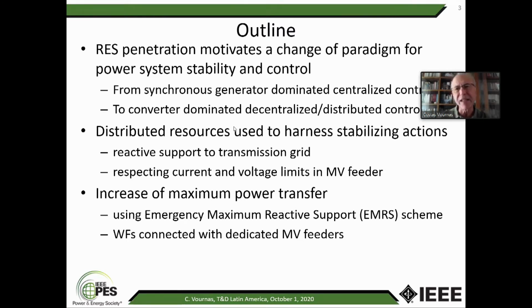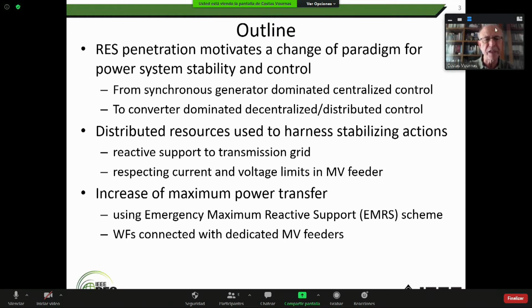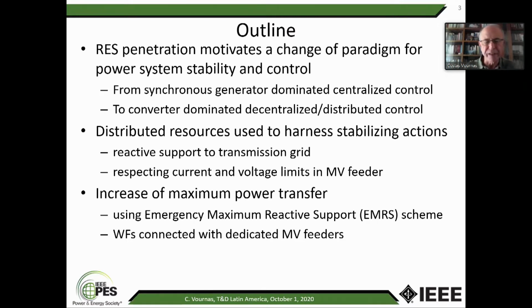Now, what I mean by dedicated medium voltage feeders is that these feeders, it is customary in the case of Greece, are only connecting the wind farm. There are no loads associated. And this is an important aspect, because if you have loads associated in the same distribution feeder with the distributed generation, then you have an effect of the generator controls, especially voltage controls, on the load consumption. So things will become more complicated if you have in the same feeder both load and generation. The case I'm describing today is simpler in the sense that we only have a wind farm connected in the MV feeder, and in this sense, I call them dedicated MV feeders.